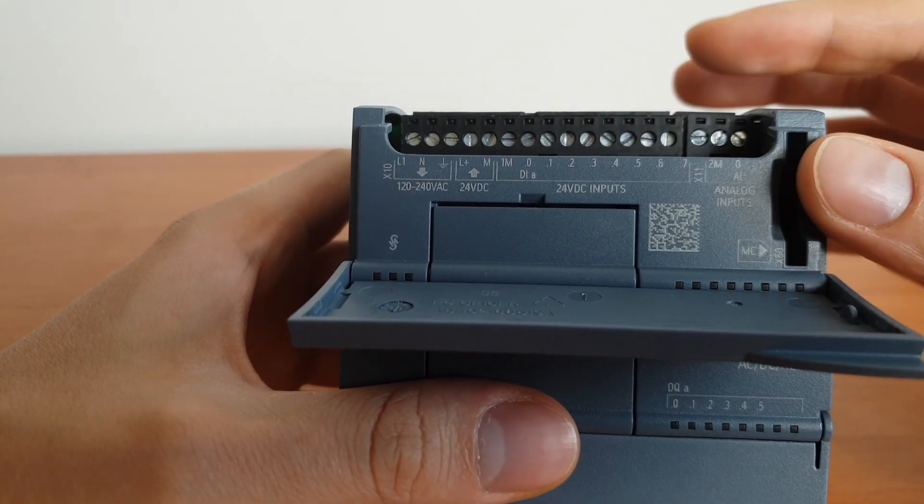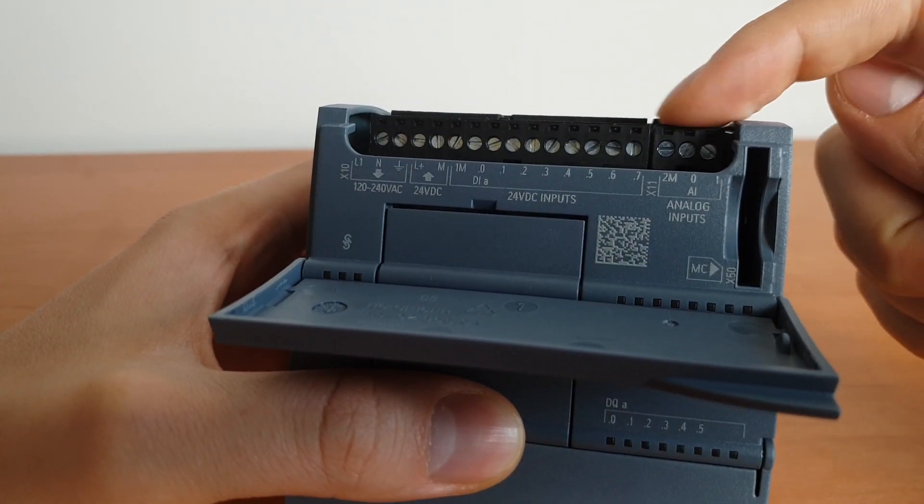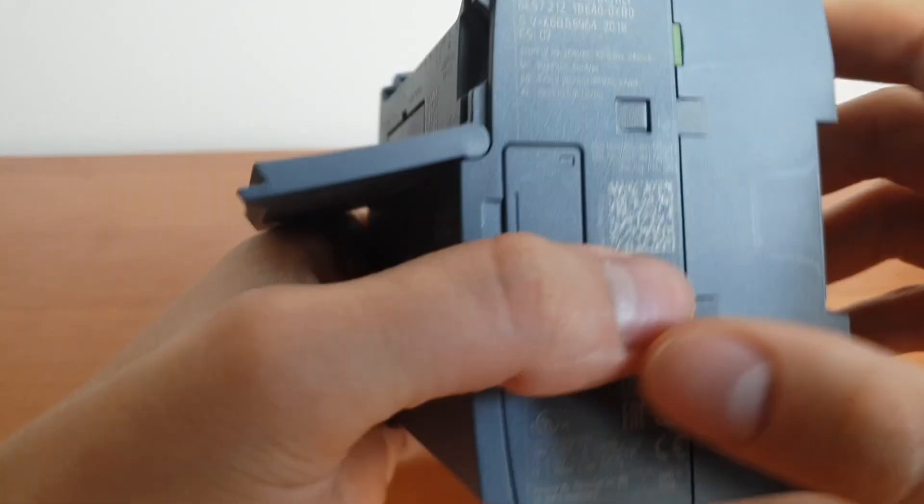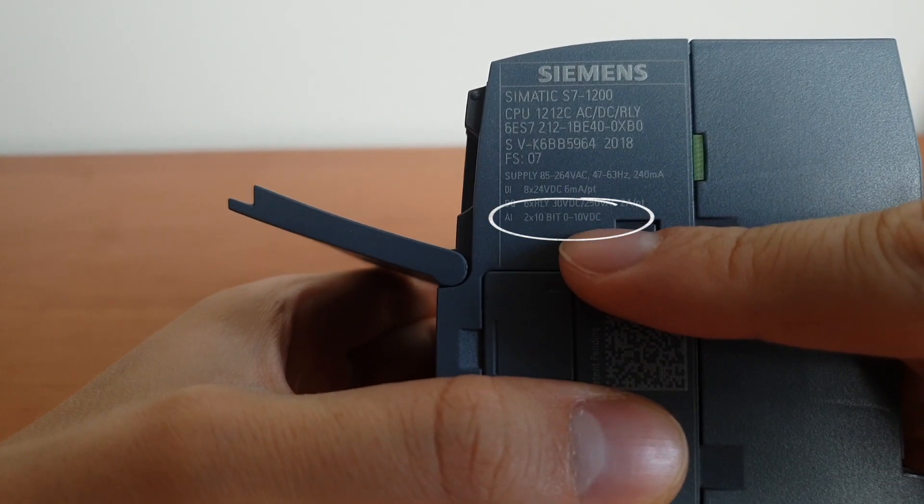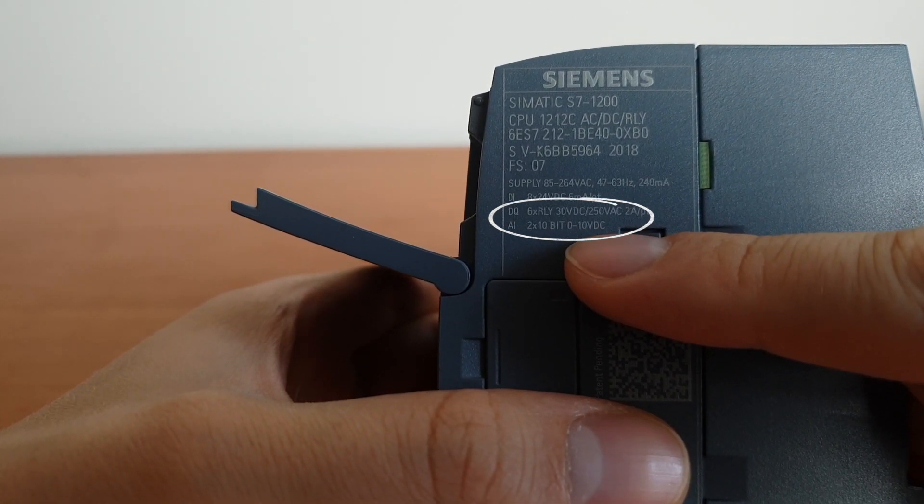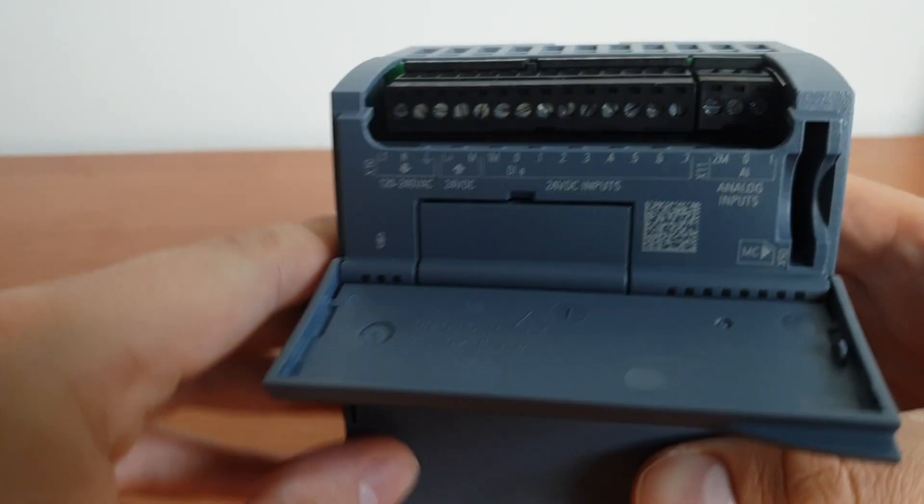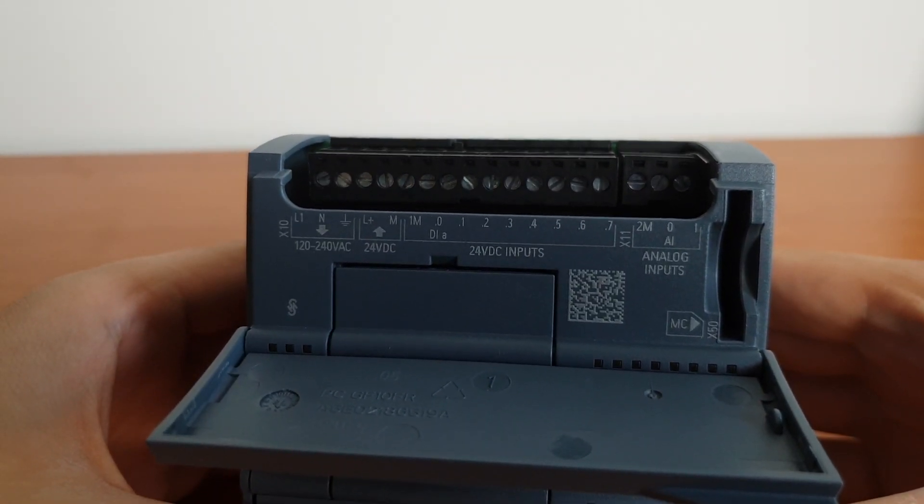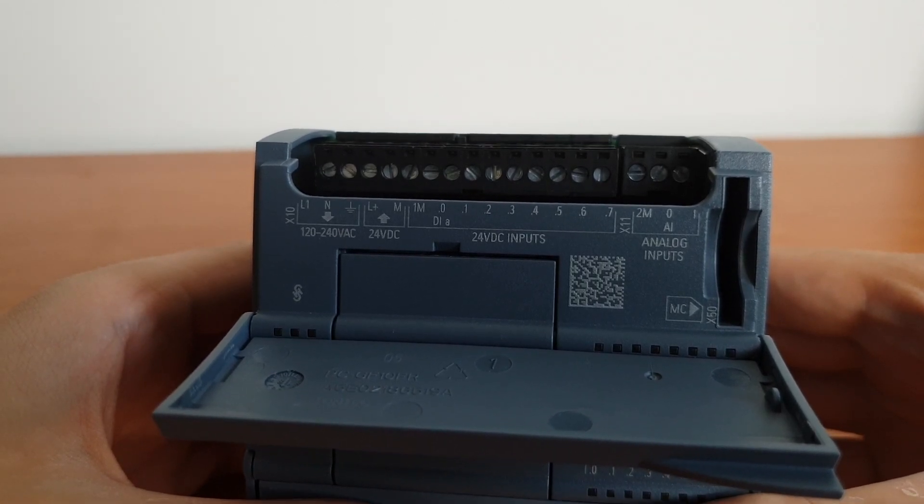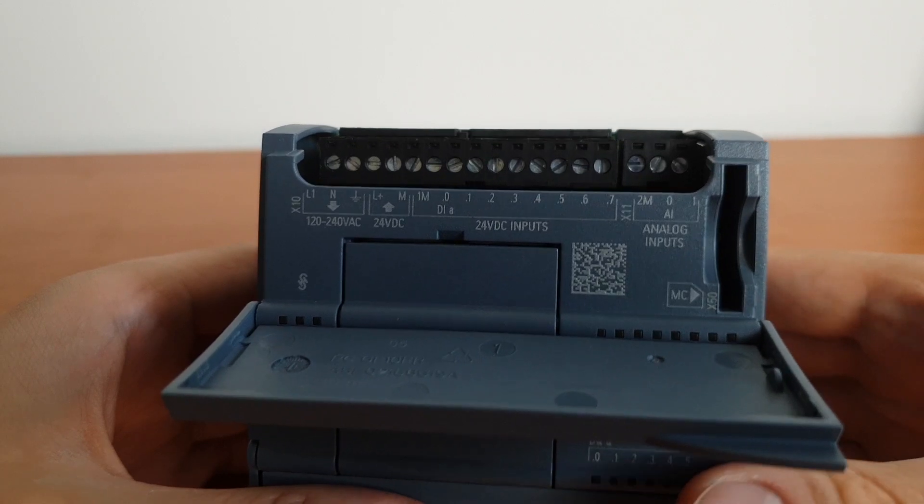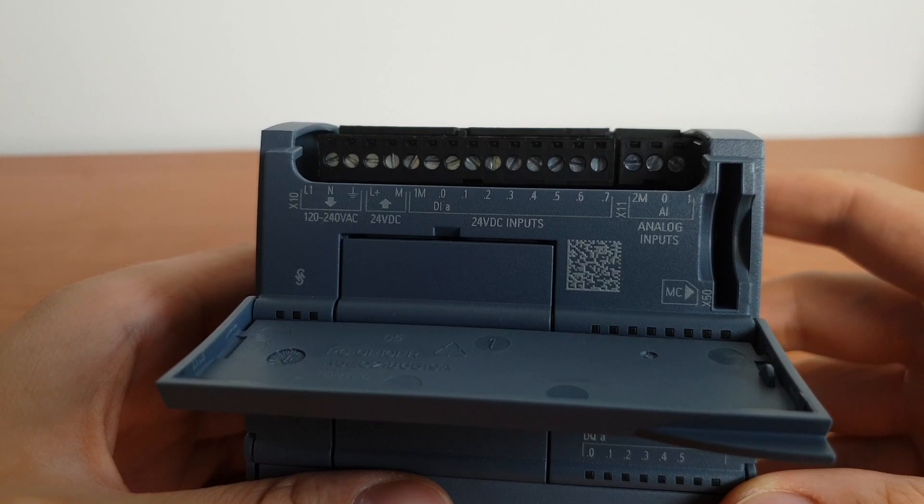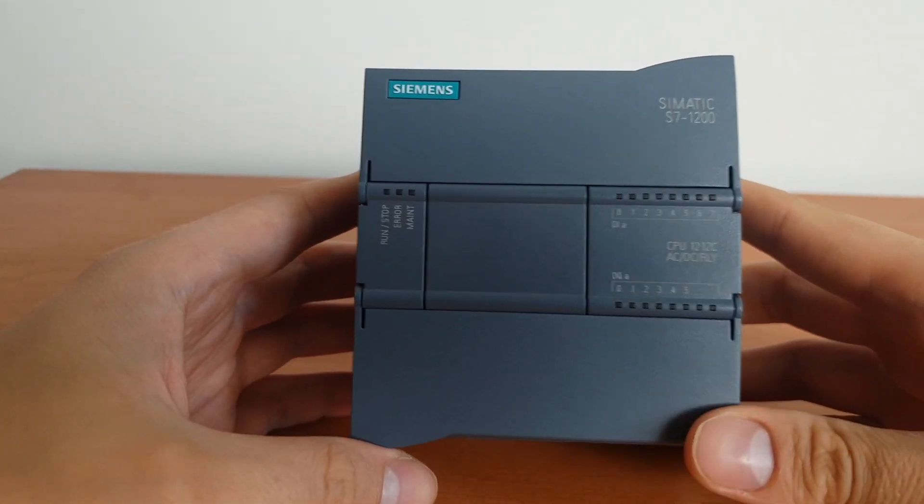So this is how digital inputs work. Now we have analog inputs. They can be different. Let's have a look here: inputs two times 10 bits resolution, zero to 10 volts DC. So there are basically two standards for analog inputs—one is zero to 10 volts, another standard is zero to 20 milliamps or four to 20 milliamps. In this case, this module accepts only zero to 10 volts.